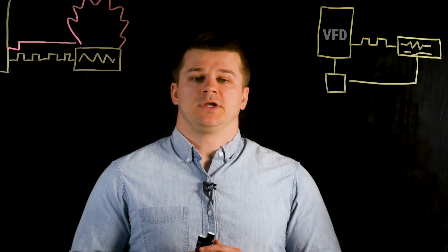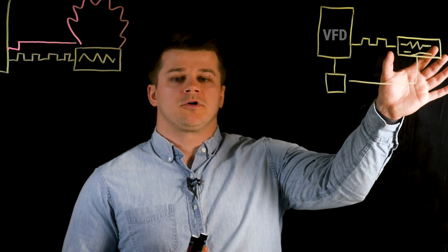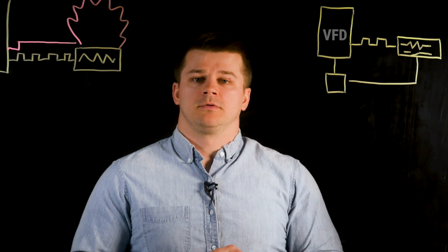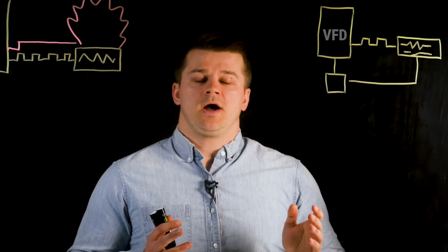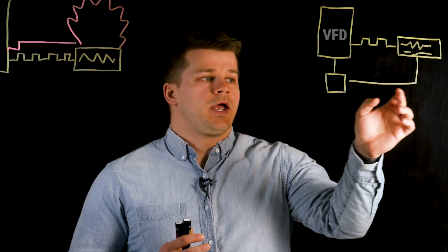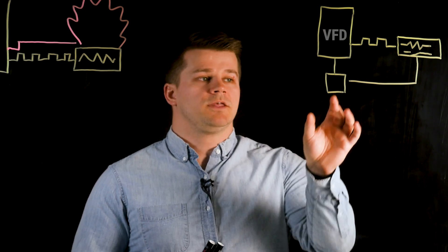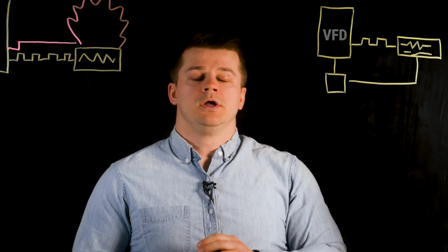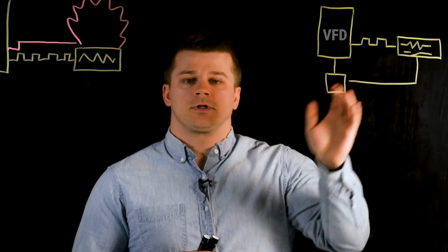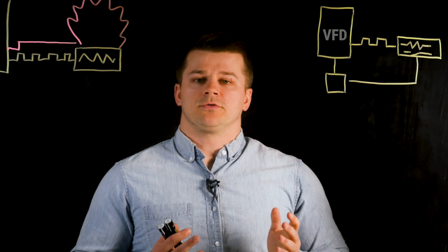The first option to protect the braking resistor is with the use of a thermal switch within the resistor itself. When the resistor gets too hot, the switch opens and it's connected to the auxiliary contact of the drive's mainline contactor. This shuts off power to the drive, so even if the transistor fails closed, there's no power going to the resistor.